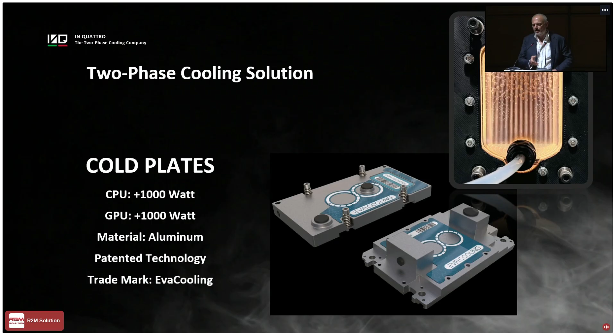We also develop patented technology. We have some patents on the geometry and the surface treatment of the heat transfer microchannels. This is important because two-phase cooling needs some specific microgeometry of the channels of the evaporative surface. In the top right of the slide, you can see an example of what happens inside a typical heat exchanger that we call the evaporator, which is attached to a processor to be cooled. And you can see the evaporation that occurs inside.